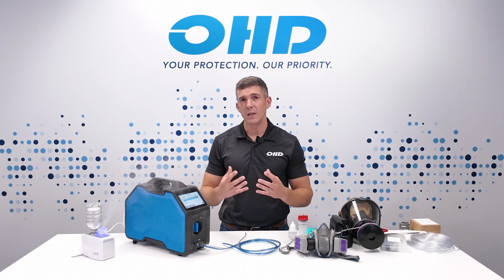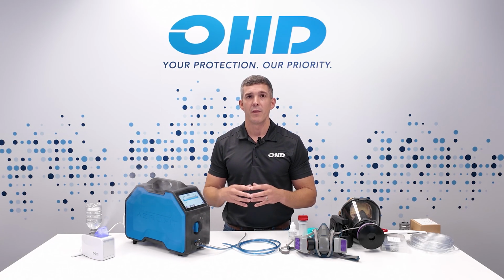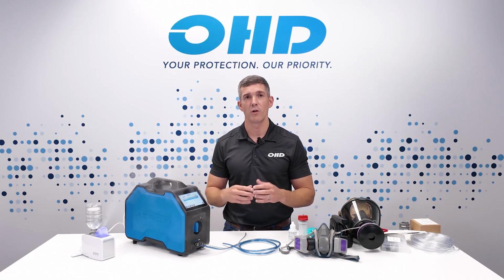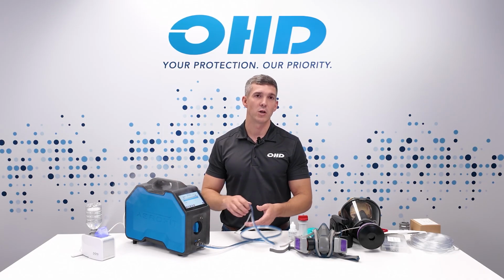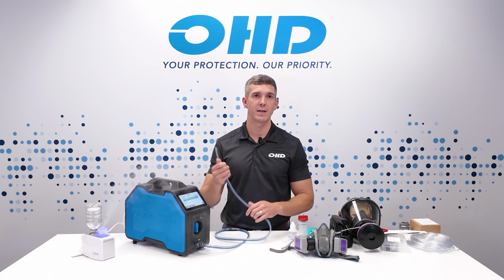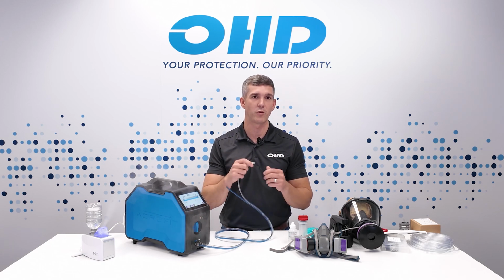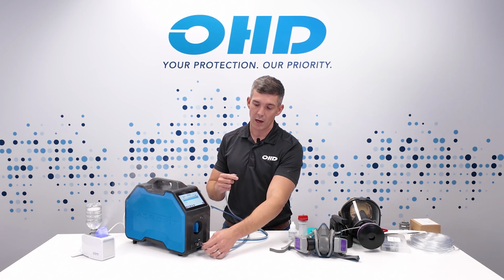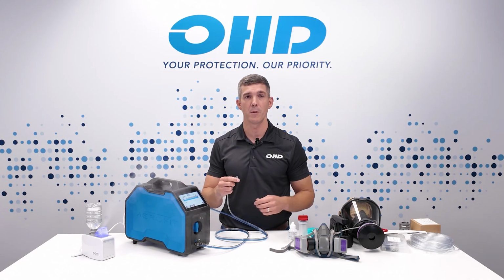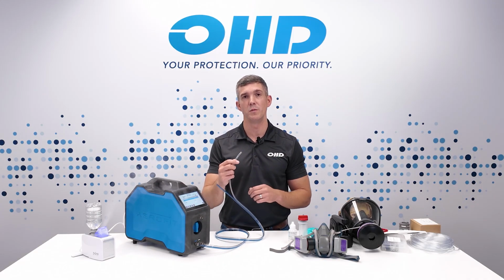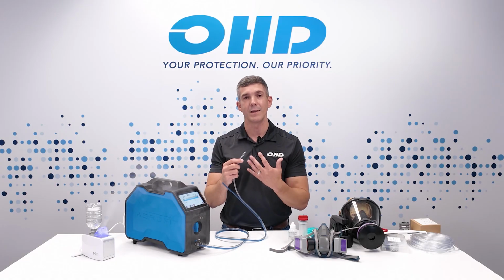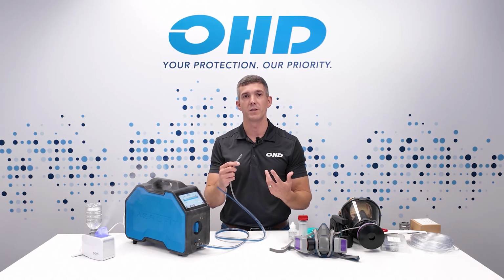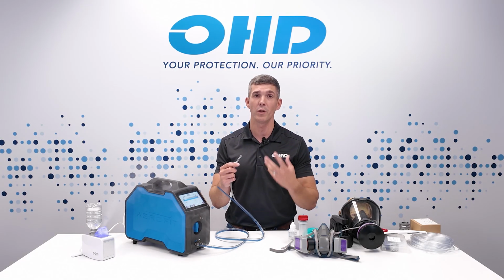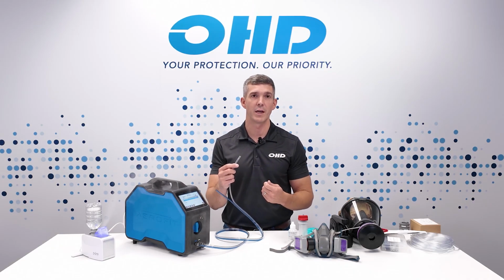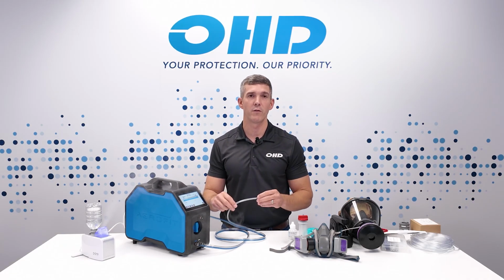As far as daily verification failures go, the main things that you want to check here are your dual tube's integrity. So at times, if you're doing a lot of fit testing, you can be connecting adapters on and off respirators, connecting up to the front of your AeroFit here. And any punctures in this tube set will obviously allow leaks into the sample, which causes issues in not only fit testing, but really more importantly, daily verification. So you want to look at the integrity of your dual tube.